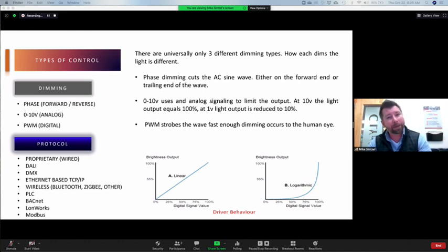DMX you could do LLLC, and DALI you could do LLLC, but any of the other ones, it's like PoE is evolving to the point where we could get luminaire level lighting control, because PoE systems, they're singly addressable on each fixture. So technically you have LLLC, but you don't have the sensors built into every single fixture, or even a lot of the fixtures. In a lot of the PoE systems, the sensors are still separate.